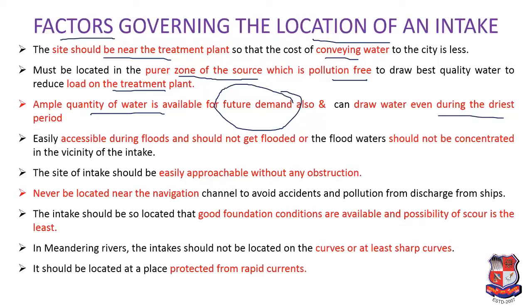Also, it should be easily accessible during floods and should not get flooded. Under such conditions, it is very difficult to operate the intake structure, and that will hamper your water supply scheme. The site of the intake should be easily approachable, because for maintenance purposes the person has to go to that particular site. Also, it should not be located near the navigation channel, because if some movement is there, chances of accidents and pollution are always there due to the movement of ships.